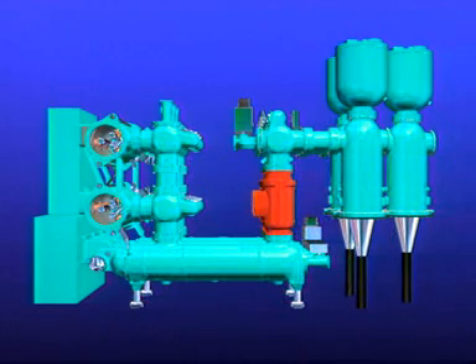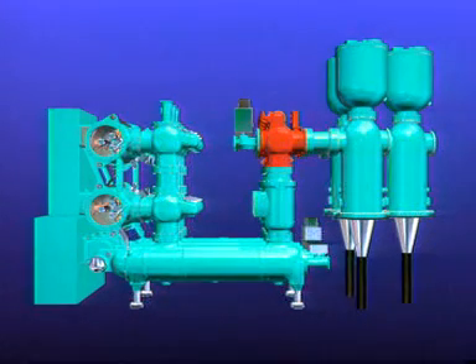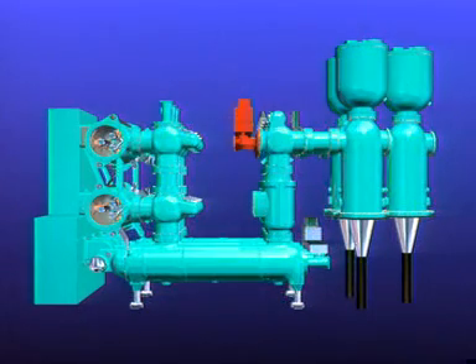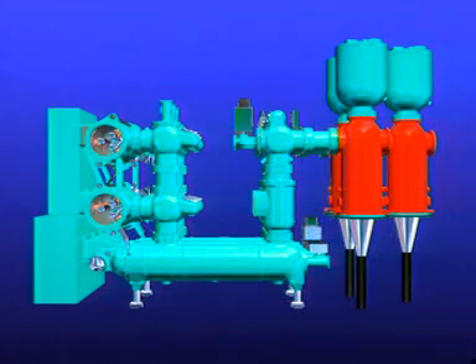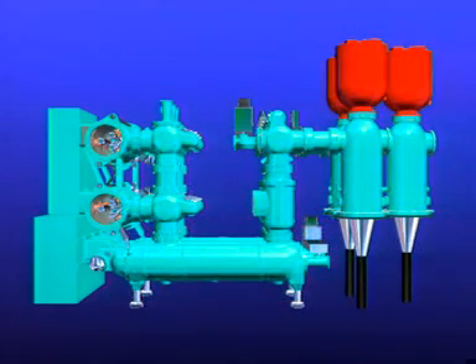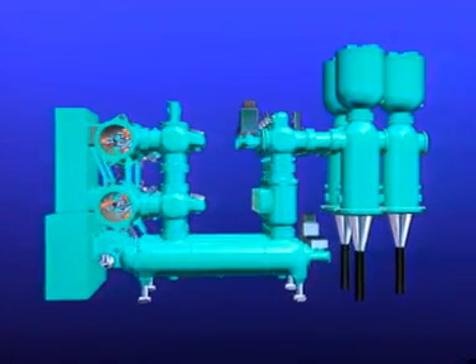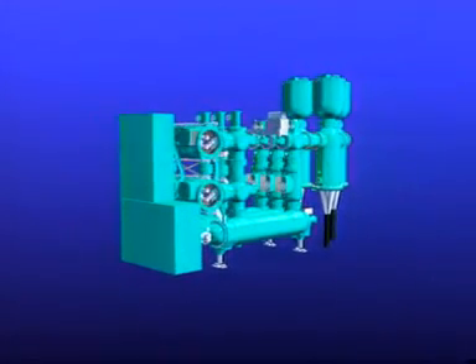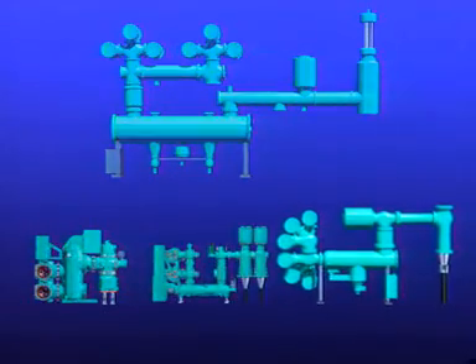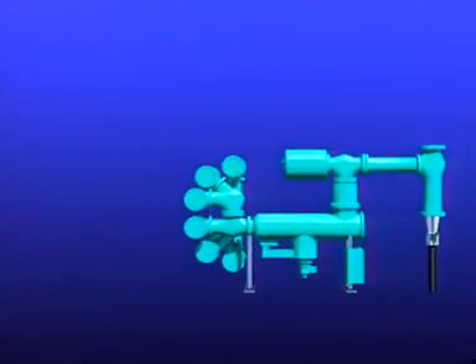For measurement and protection tasks, an inductive current transformer is installed after the circuit breaker. Above it, we find the feeder disconnector, the make-proof earthing switch with its stored energy spring mechanism, and above the cable sealing end, the inductive voltage transformer in a gas-tight enclosure of its own. The proven switchgear for voltage levels above 245 kilovolts likewise benefits from progress in application and production technology. Here is an 8DQ1 for voltages up to 550 kilovolts, for instance.